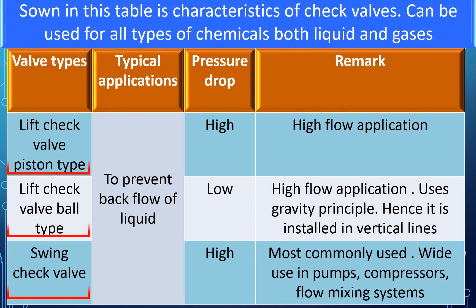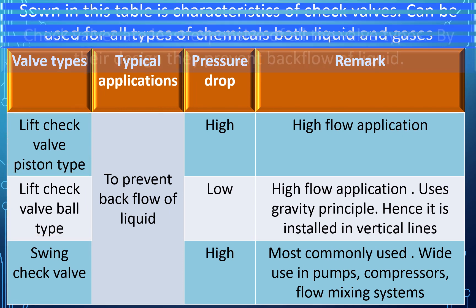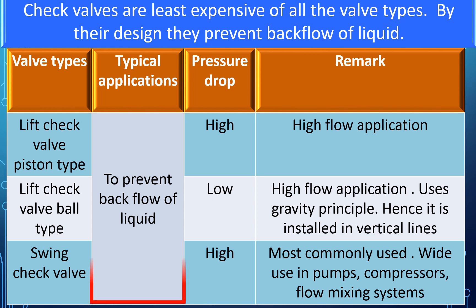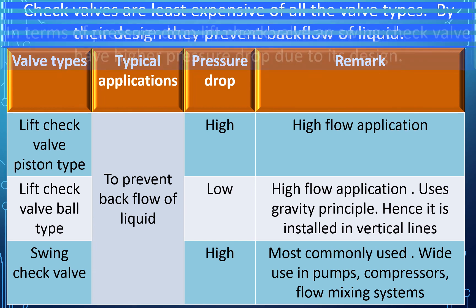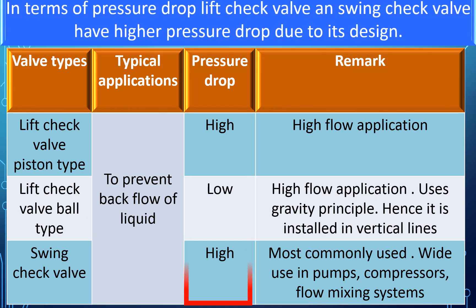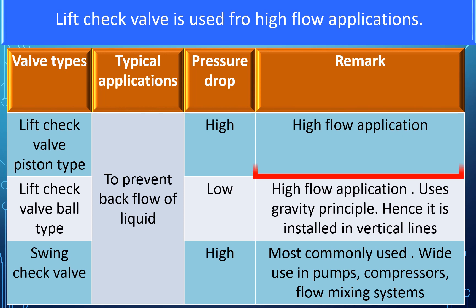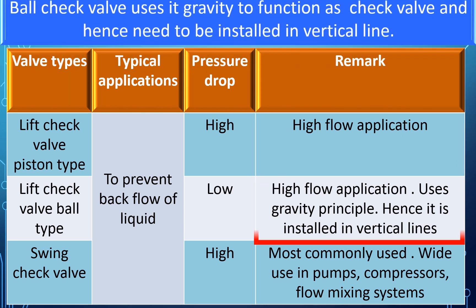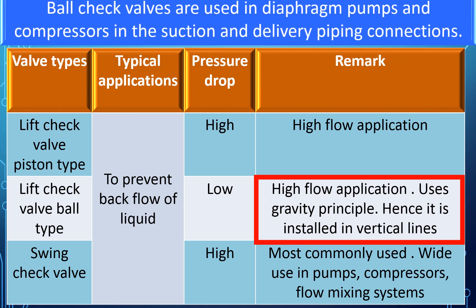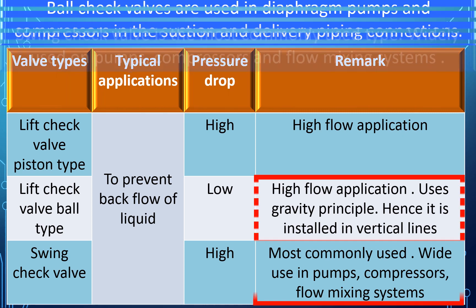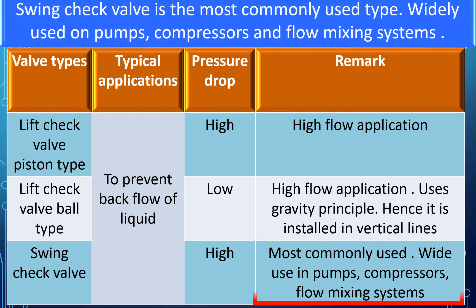This table shows the types and characteristics of check valves. They can be used for all types of chemicals, both liquids and gases. Check valves are the least expensive of all valve types. By design, they prevent backflow of liquid. Lift check valves and swing check valves have higher pressure drop due to their design. Lift check valves are used for high flow applications. Ball check valves use gravity to function and hence need to be installed in vertical lines. Ball check valves are used in diaphragm pumps and compressors. Swing check valves are the most commonly used type, widely used on pumps, compressors, and flow mixing systems.